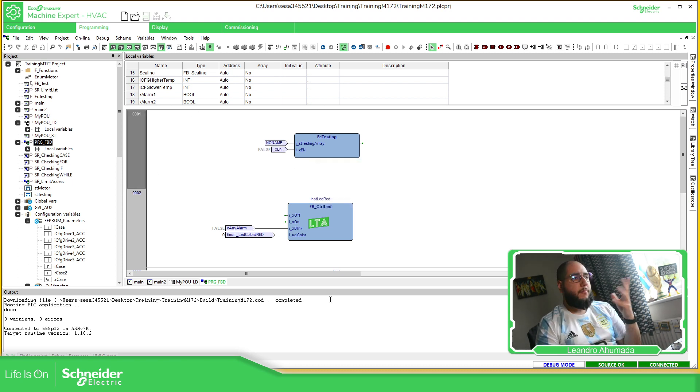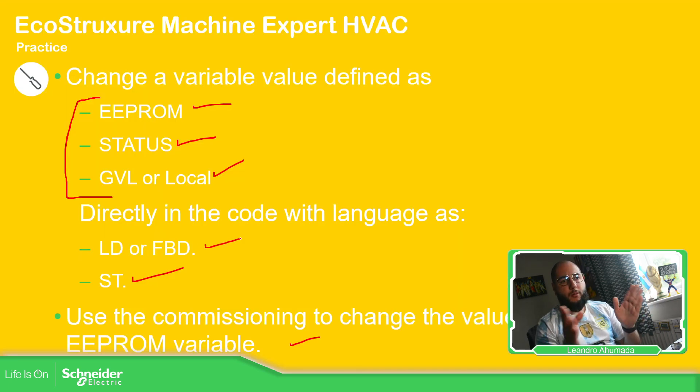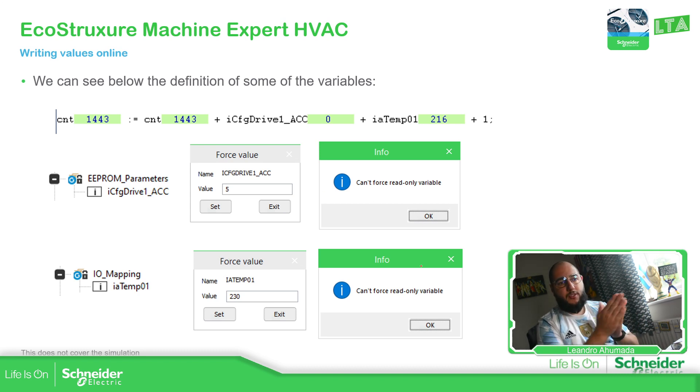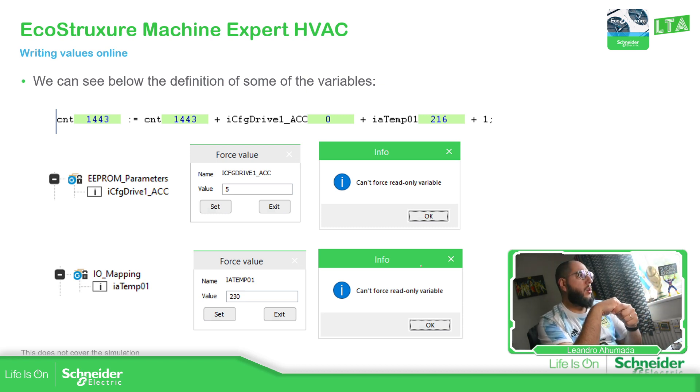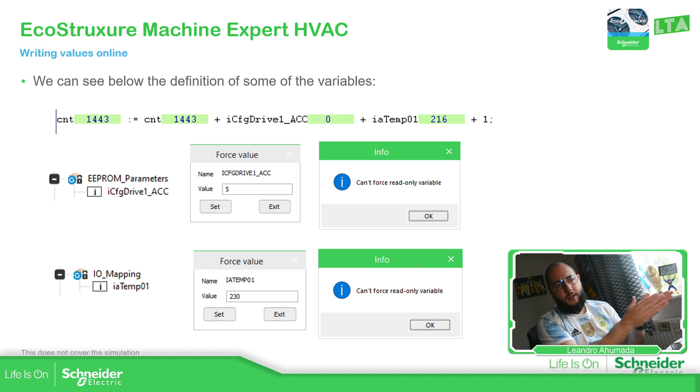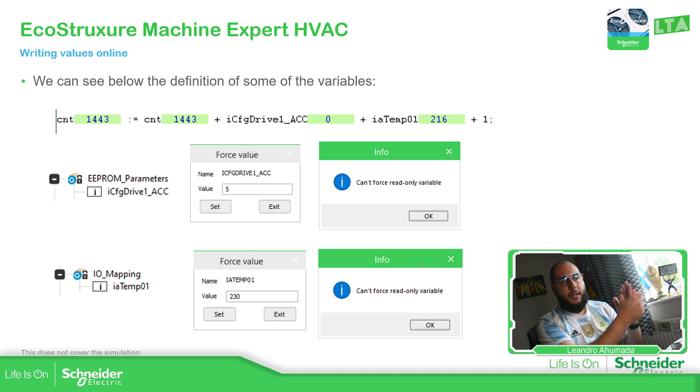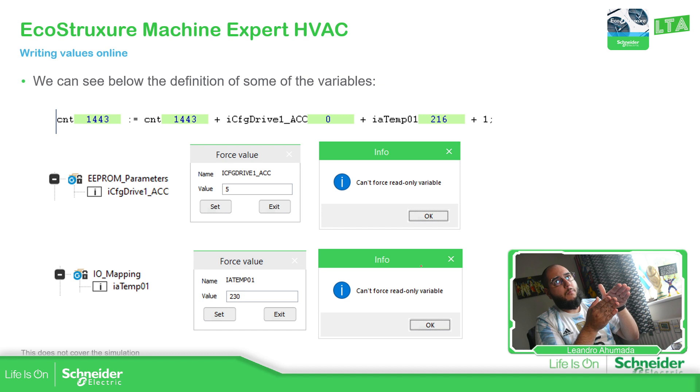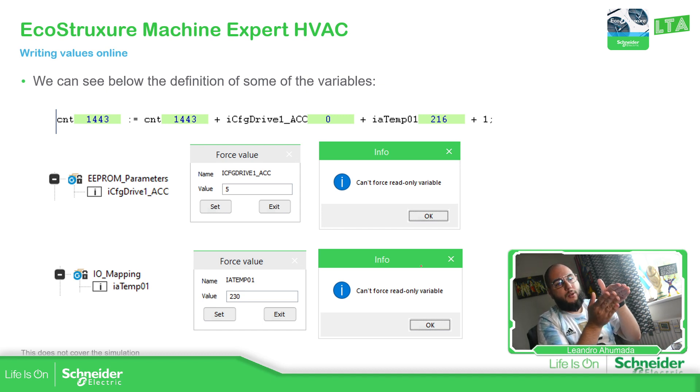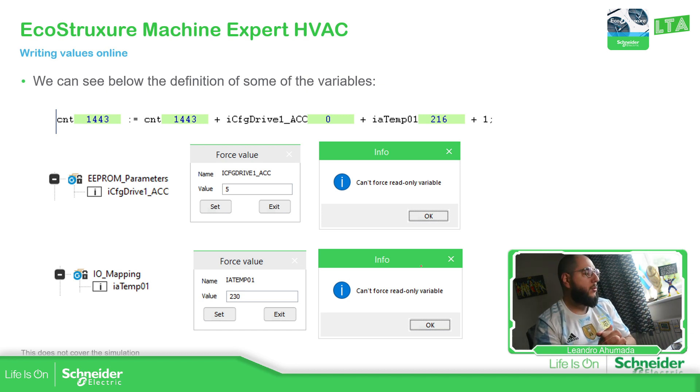So basically the idea here is to show that in order to change the value, just double click on the variable. And if you see this message, okay, it means something happened. It could be there is an EEPROM. Then if it's an EEPROM, you just need to use commissioning to change it. Or if it is the IO mapping variable, you can't change it because it came from a sensor for that. You probably need an additional function block that you can create, so you can define which value you need to choose from this one or this one, when you select if it's your maintenance mode or not. Something like that you can do.